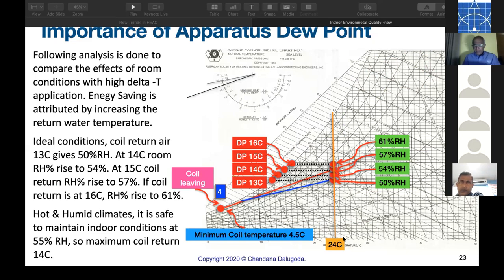We raise the chill water outlet temperature to 14, the resultant RH will be 54. If the dew point is 15, RH is 57, then 61. So now we can see there's a limit. Keep that in mind when we discuss high delta T applications. We have a limit. We can't go like that.